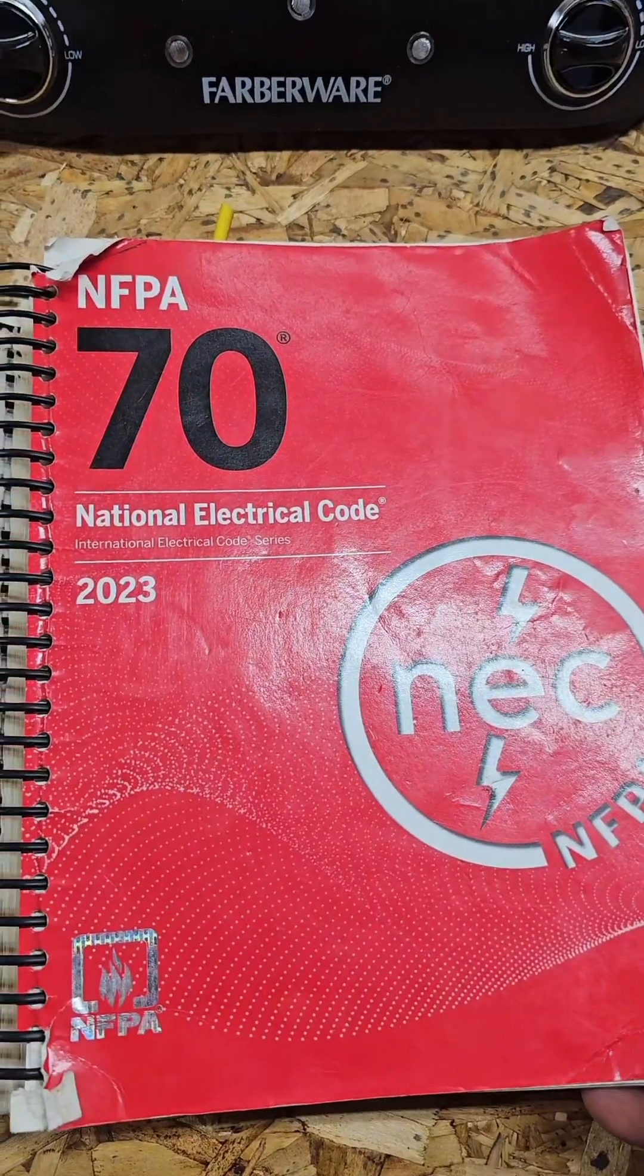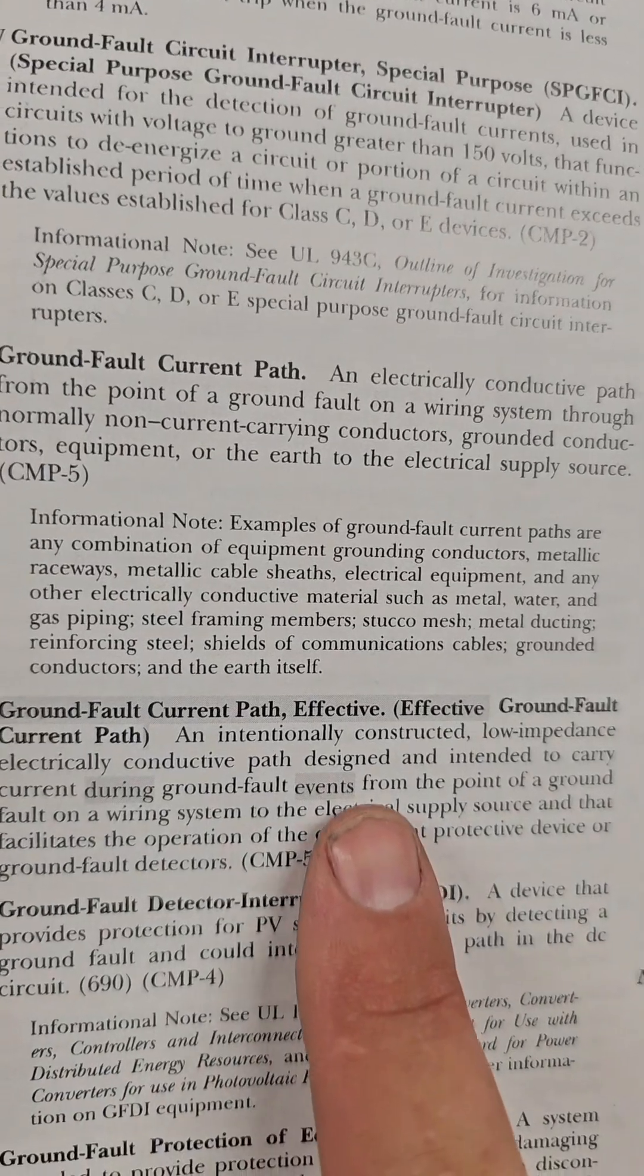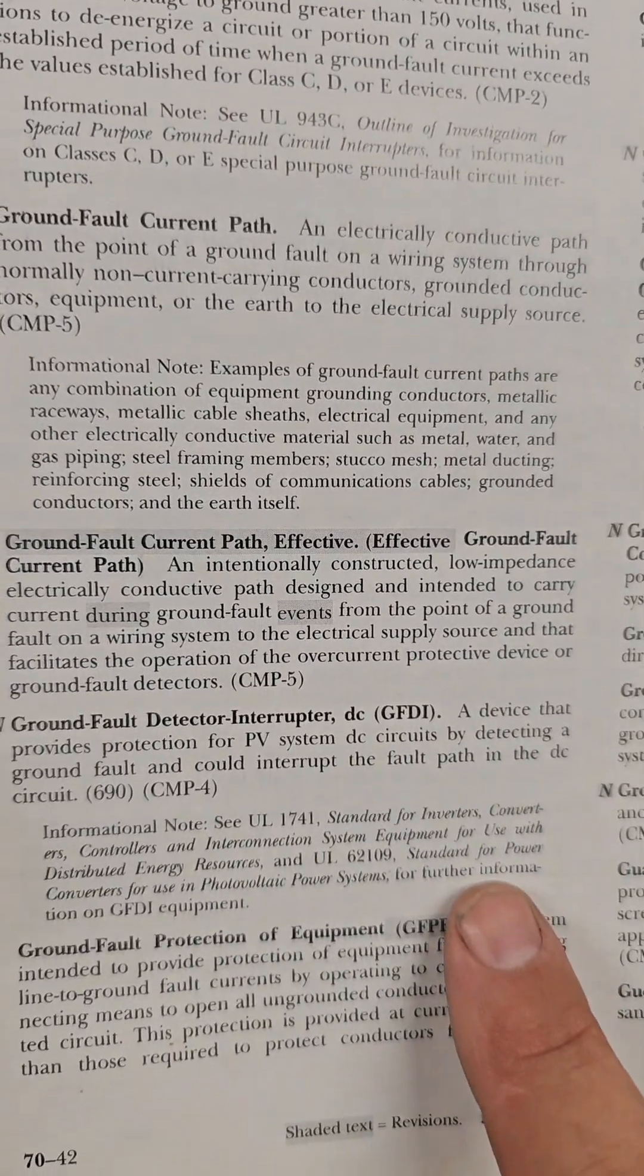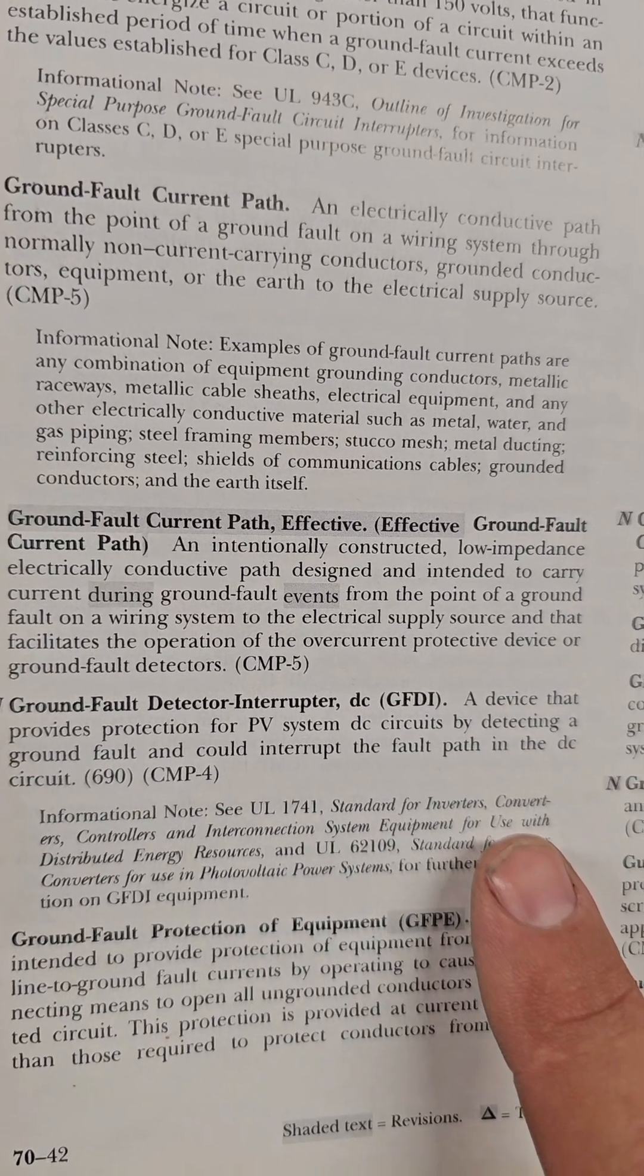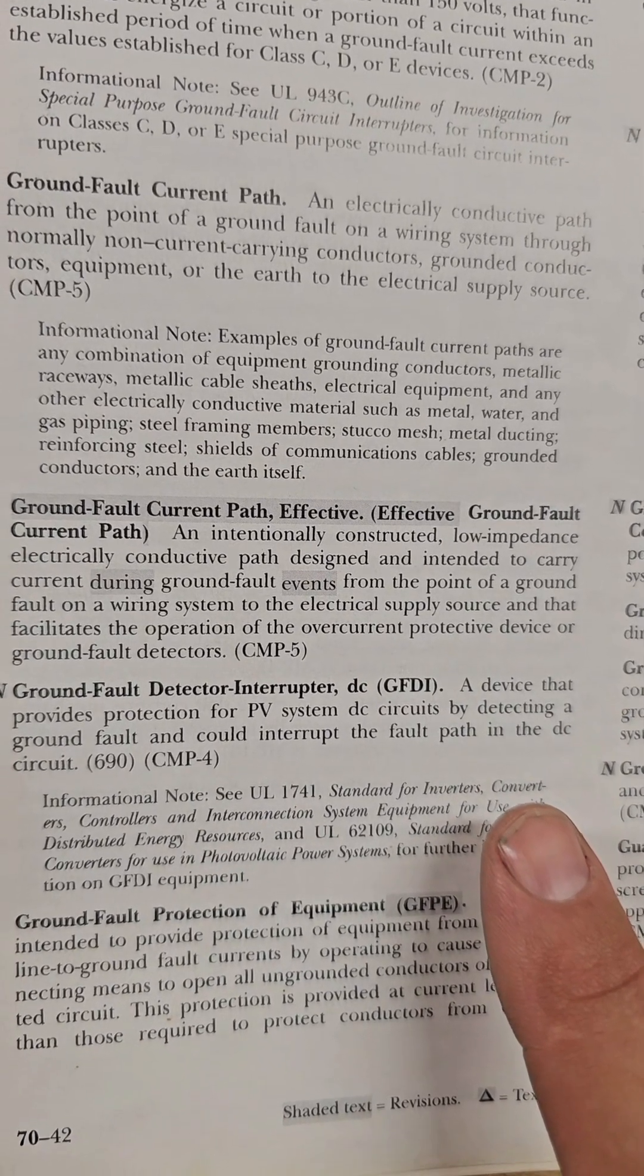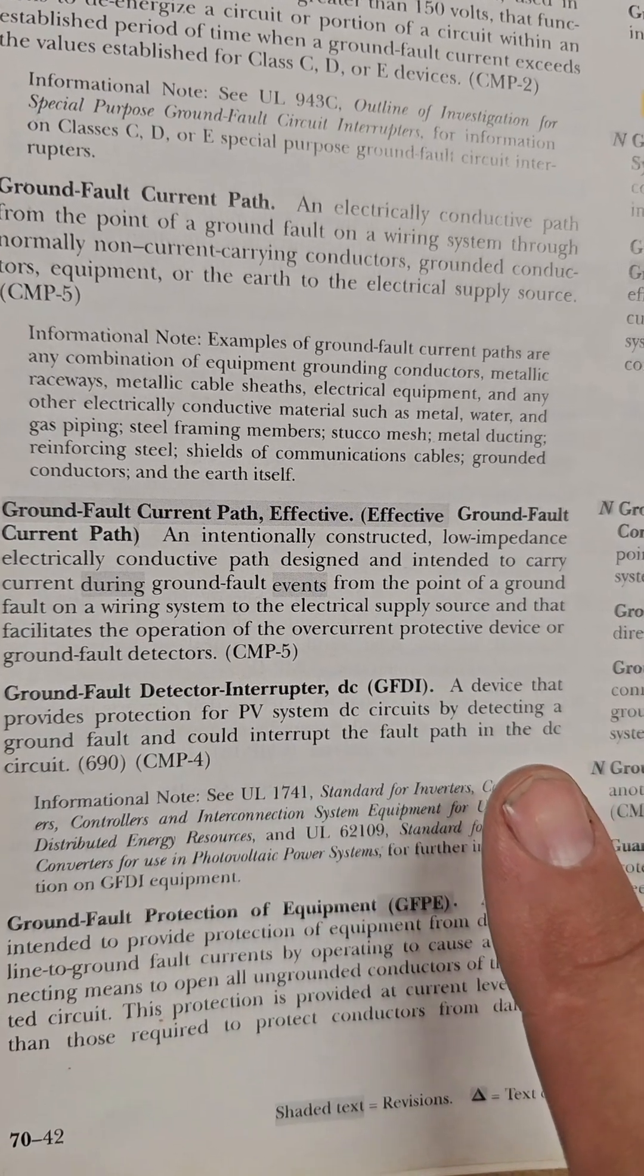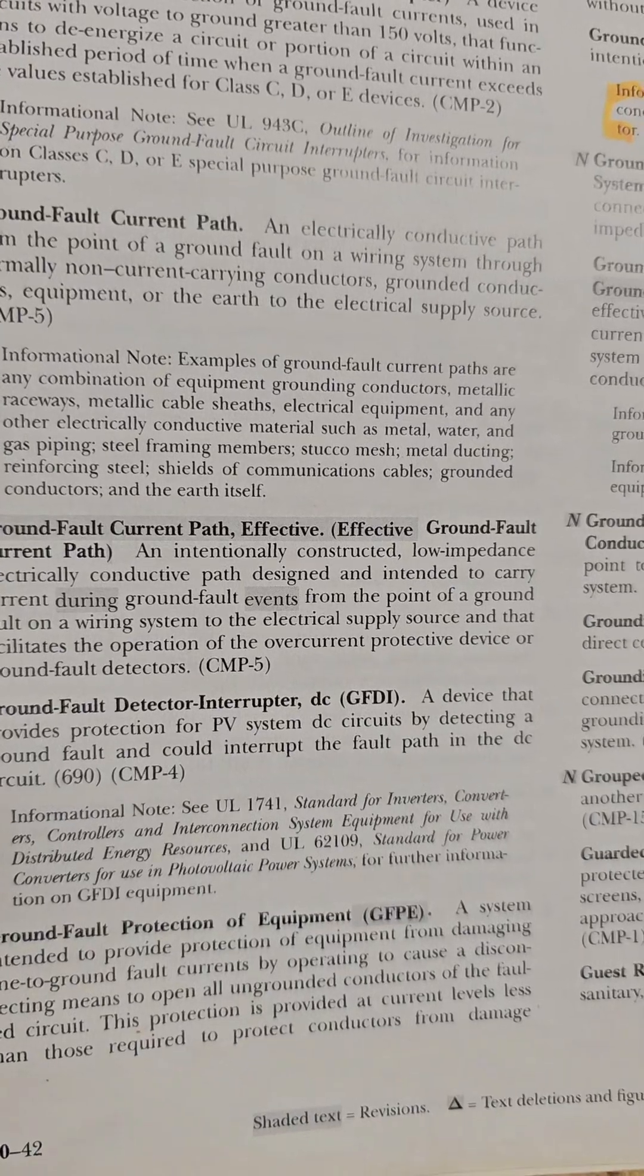So the definition has been changed a lot over the years, and I really like the definition in the 2023 code for what is an effective ground fault path because the word earth is not even in the definition. Let's look. All right, we're in the 2023. If you go to definitions, you have a ground fault path, but you have an effective ground fault path. So if you read the definition for effective ground fault path, an intentionally constructed low impedance electrically conductive path designed and intended to carry current during ground fault events from the point of the ground fault on the wiring system to the electrical supply source that it facilitates the operation of an overcurrent protection device. There's no mention of the earth in this definition.